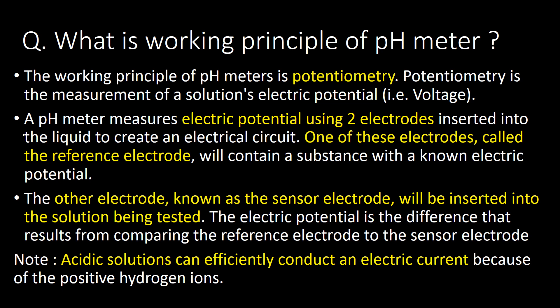A pH meter measures electric potential between two electrodes that are inserted into the liquid to create an electrical circuit. One of these electrodes, called the reference electrode, contains a substance with a known electric potential. The other electrode, known as the sensor electrode, is inserted into the solution being tested. The electric potential is the difference that results from comparing the reference electrode to the sensor electrode.